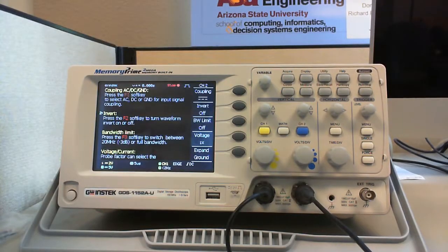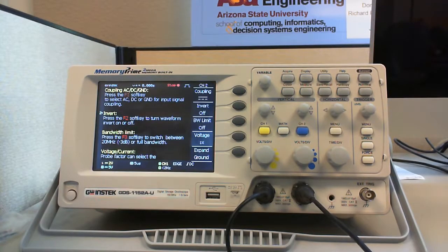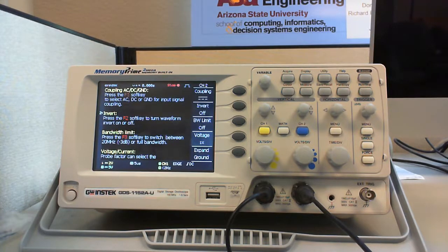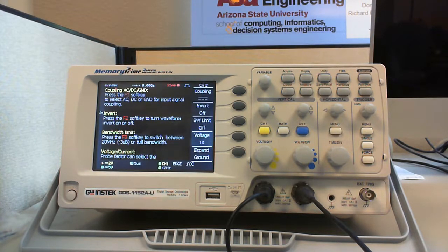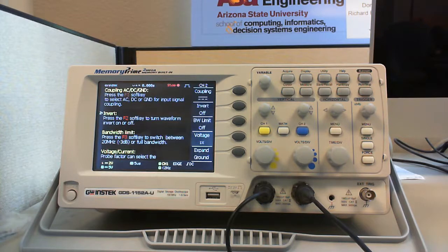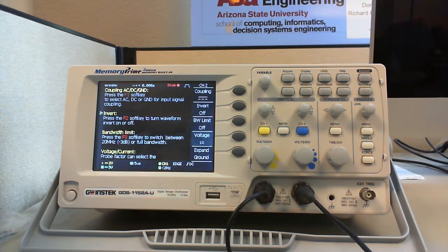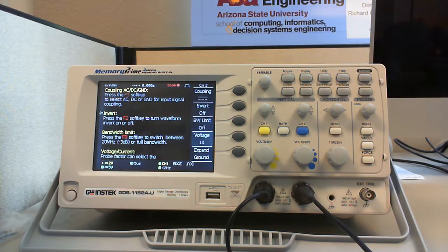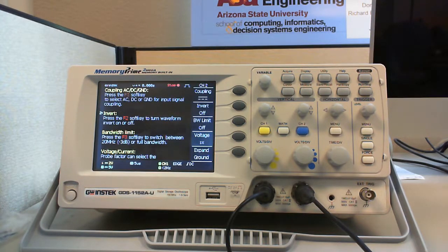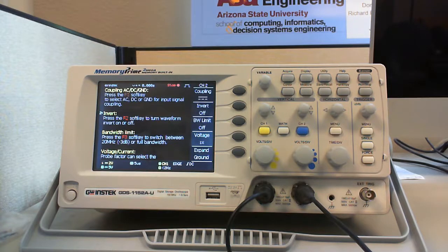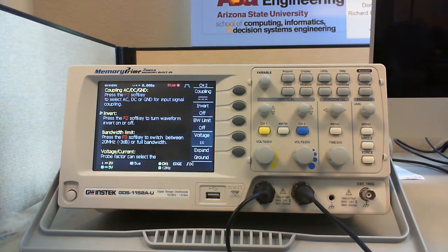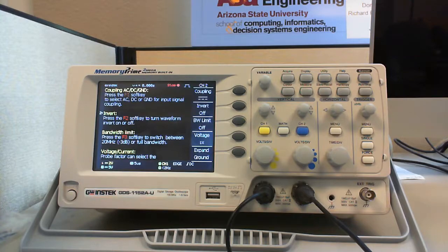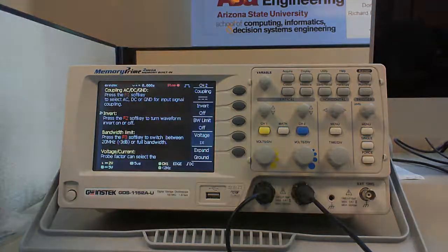So these are the functionalities of the different keys present on the DSO. A DSO can sometimes be used as a digital multimeter as well. Whenever you want to measure DC voltage between two points, just connect the probe tip connection to the positive side and ground it properly and press the measure button so that the DC voltage will be displayed on the screen. Though you won't be able to see the waveform of the DC voltage as there is no frequency. Thank you for watching.